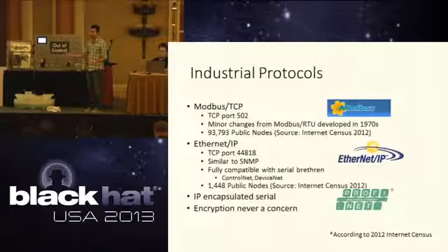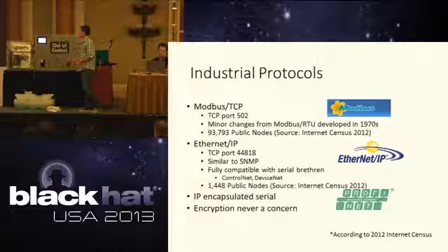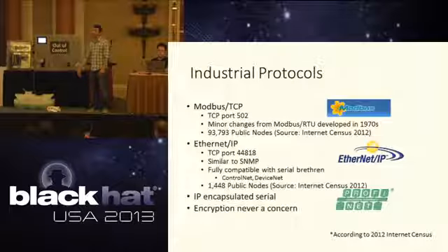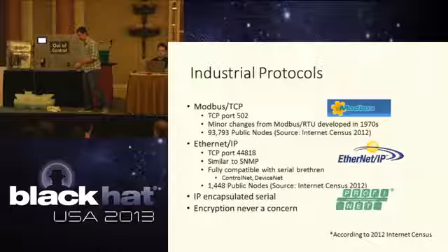So we'll talk a little bit about industrial protocols. So we have a couple of them. The one that we find most important is this Modbus TCP protocol. It's TCP port 502, and it's been around since the 1970s in serial form.